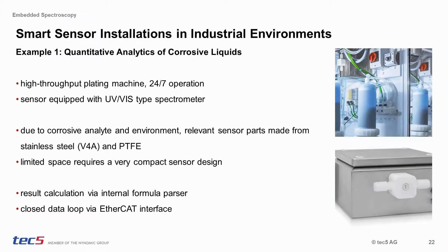In our first example, a UV-Vis-based smart sensor is used for quantitative analysis in liquid phase. The smart sensor is integrated into a high-throughput plating machine aiming to ensure reproducible product quality. Harsh environmental conditions as well as corrosive analytes require the smart sensor to be set up in stainless steel housing with a PTFE flow cell integrated to the sensor. It is also a good example where the result calculation is based on our internal formula parser and where a closed data loop via EtherCAT interface is realized.